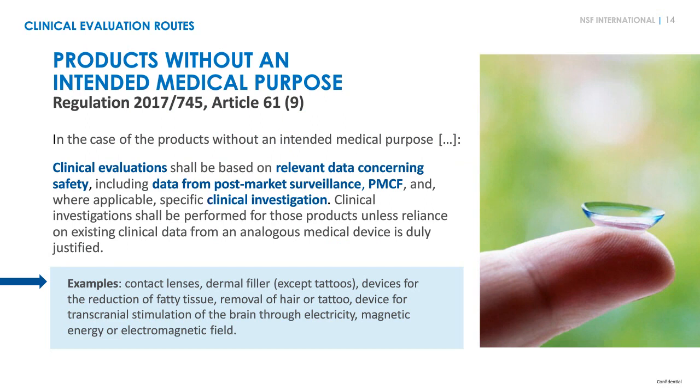Before proceeding to the potential routes to perform a clinical evaluation, I would like to spend some time to talk about a few special cases. The clinical evaluation of devices without an intended medical purpose, such as contact lenses and dermal fillers, shall be based on relevant data concerning safety, and the demonstration of clinical benefits should be understood as a demonstration of performance. In this case, important sources of data are the post-market surveillance and PMCF.